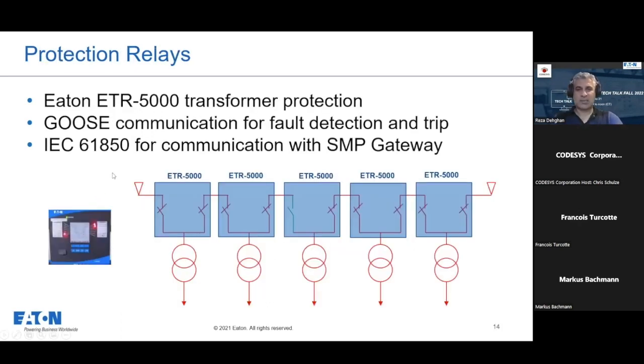So for the protection side, we use Eaton ETR 5000 transformer protection. What we were doing during the project was like a joint operation between us, the substation automation team, the transformer team, and also the relay team, who were doing some design at the same time with the relays. So we always had to communicate with each other, make sure that everything is working on both sides of the logic.